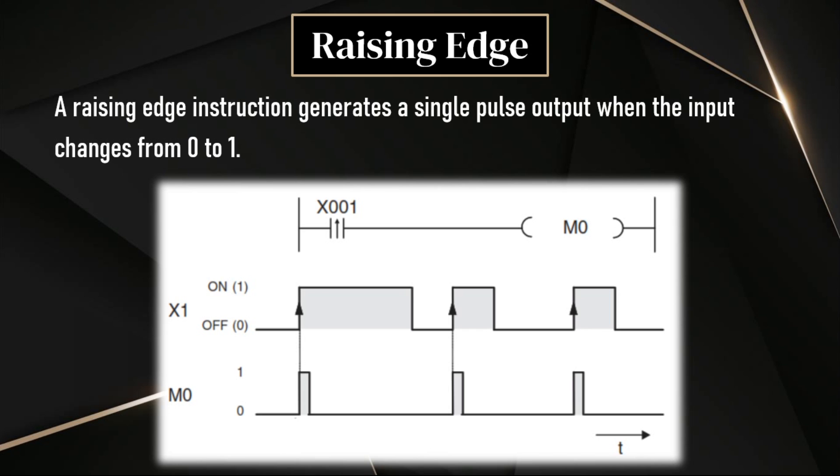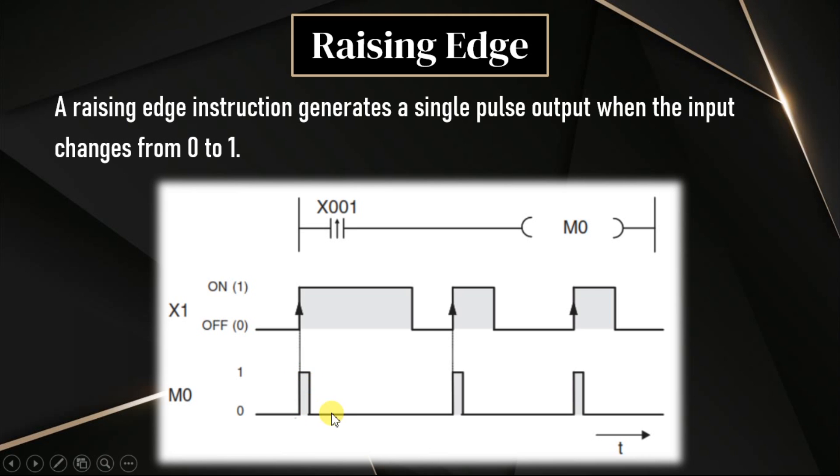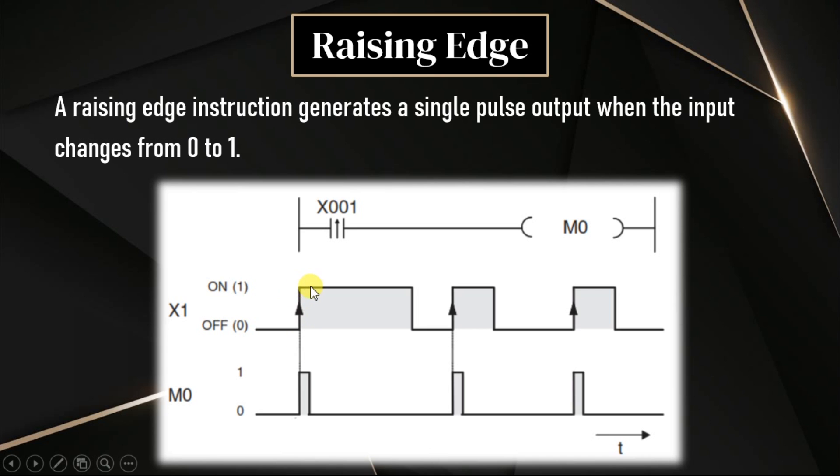For rising edge, the input must change from 0 to 1. If you see this timing diagram, whenever the input X1 changes from 0 to 1, then output M0 will be turned on for a single pulse. That means output will be a single pulse irrespective of the input duration.